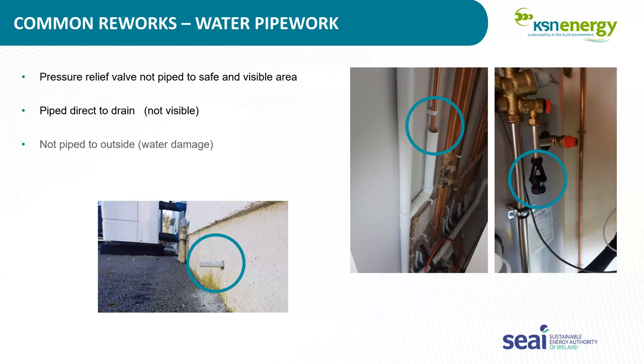Then the safety valve. So from that last slide, perhaps what's happened is someone closes the valve to the expansion vessel. The system can't take up the expansion. The system overpressurizes. That water has to go somewhere.